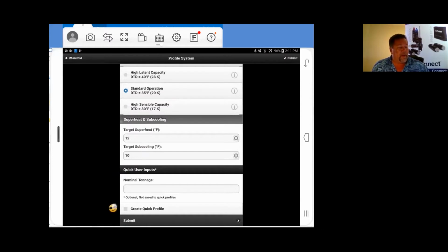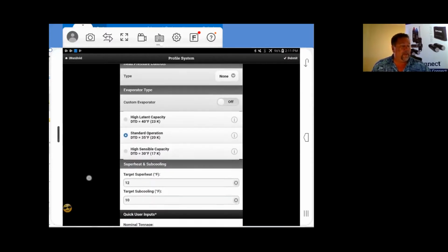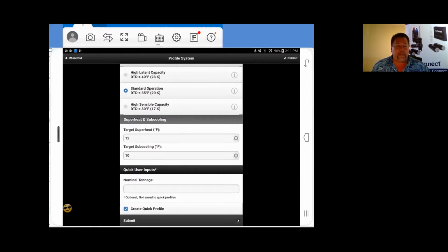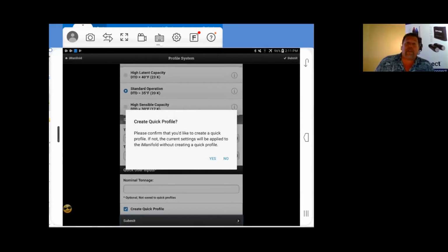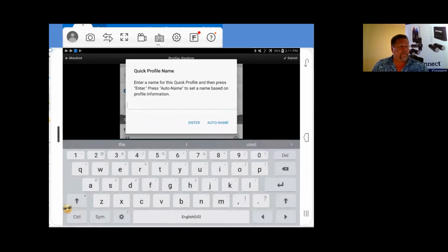And now I'm going to create a quick profile. That is as simple as it gets. The target superheat and subcooling, that's an adjustable number anyway, and you're going to take that off of the nameplate on the system anyway. So this is just the superheat subcooling that's in here. Those are just defaults. So after I selected quick profile, I submit. It's asking me if I want to create a quick profile, which I do. I'm going to say yes.